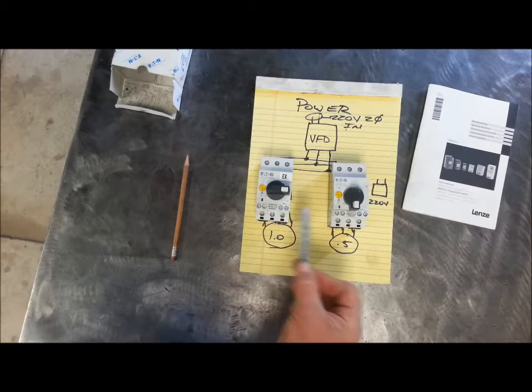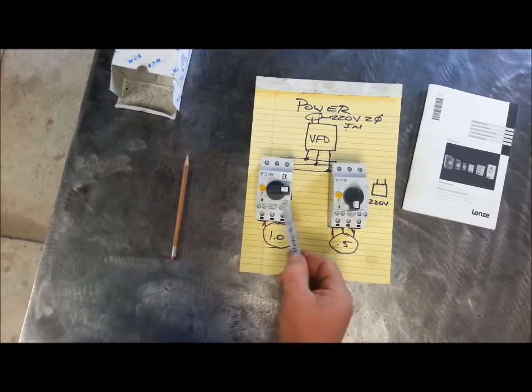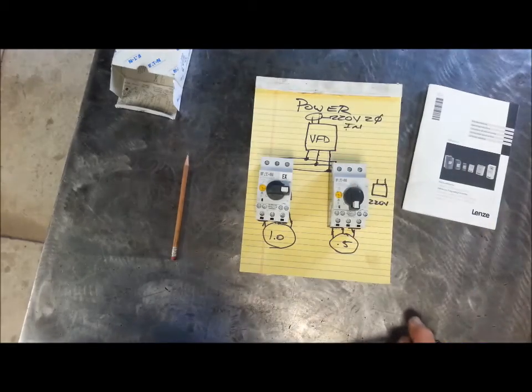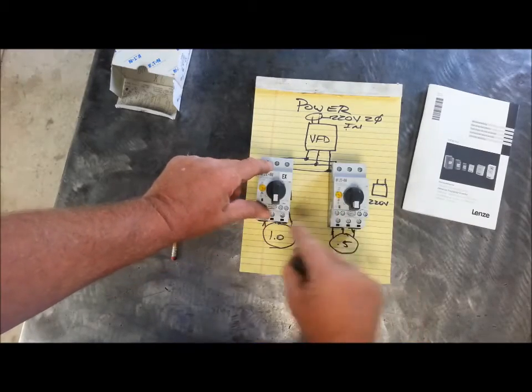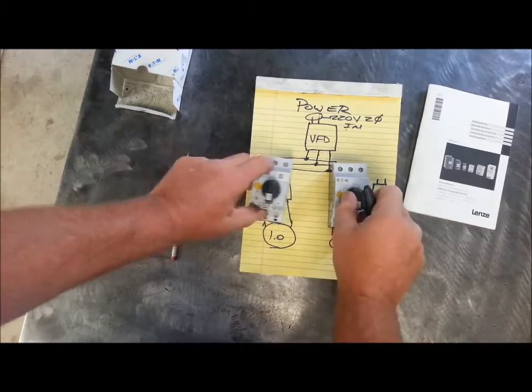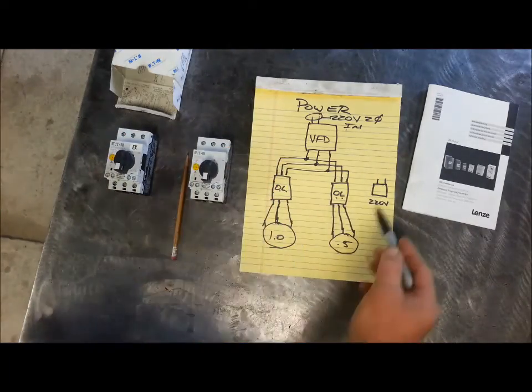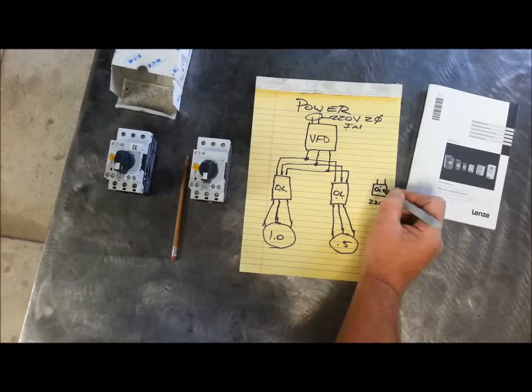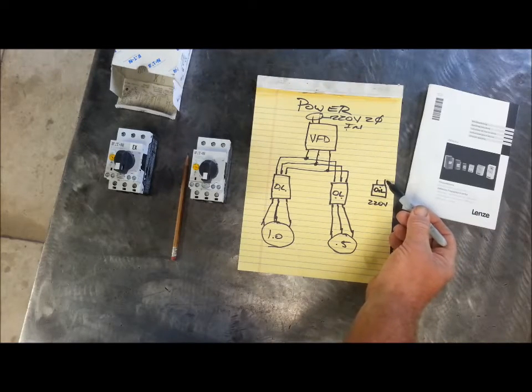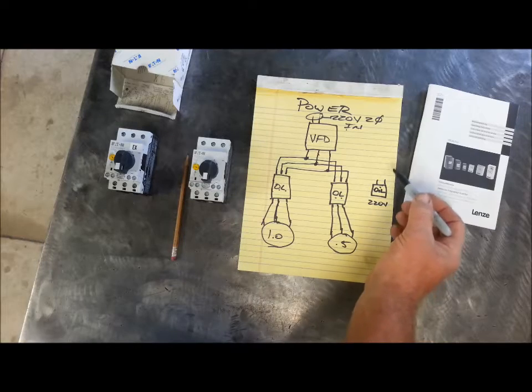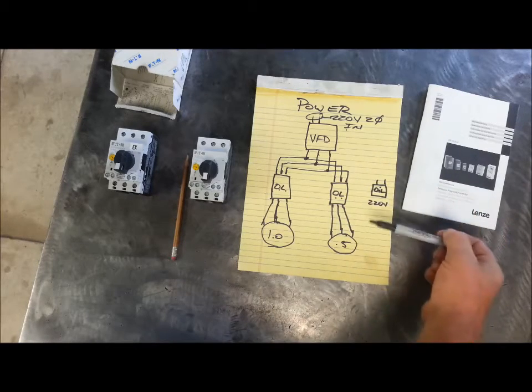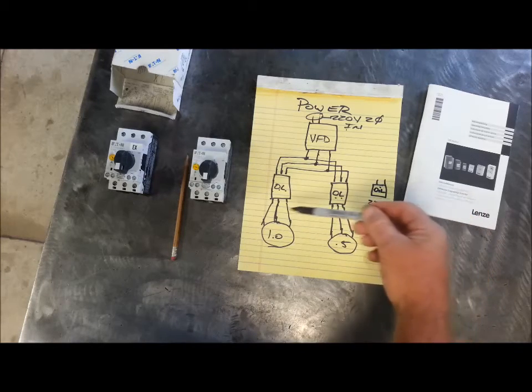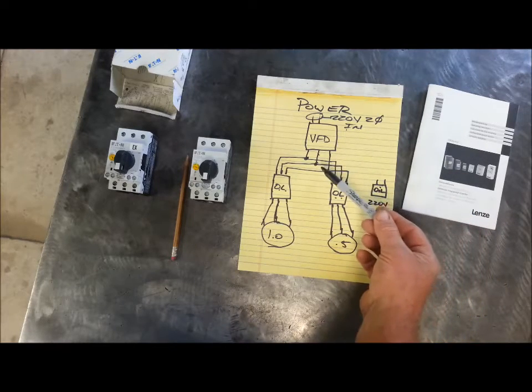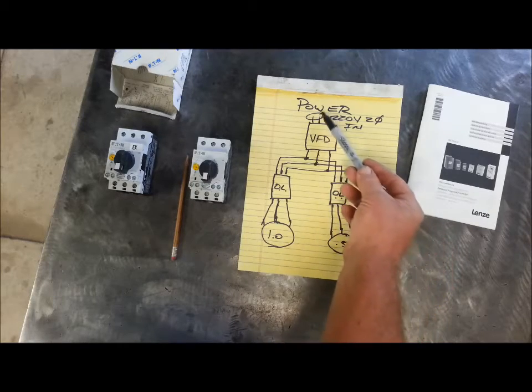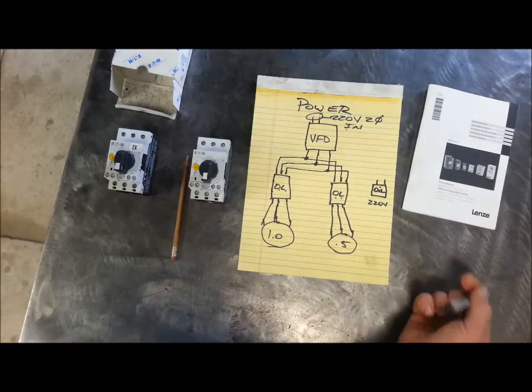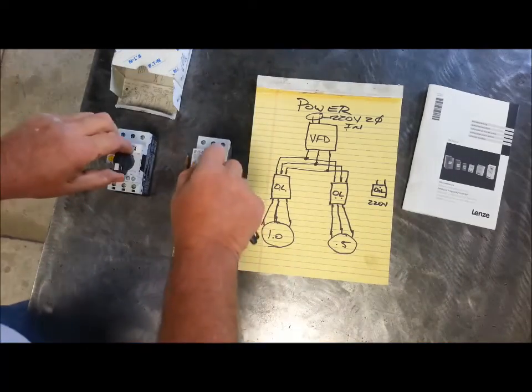So we're going to use the auxiliary switch gear on the overloads to send a feedback signal to the VFD to shut it down. And I'm going to show you how to do that on another drawing, because this is considered control wiring here and here. And also your oiler, we're going to name this oil. Your oiler is going to get wired into a control circuit as well. So anyways, this is the power wiring. I'm going to draw all these components again on another piece of paper, and we're going to name that one control. But these are all your load carrying wiring.